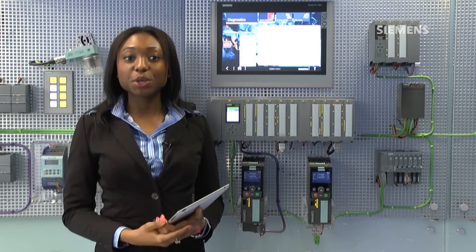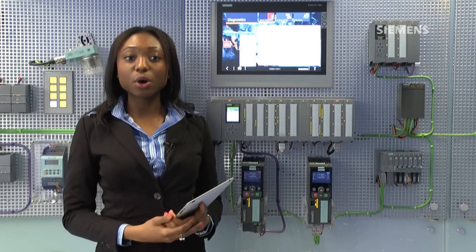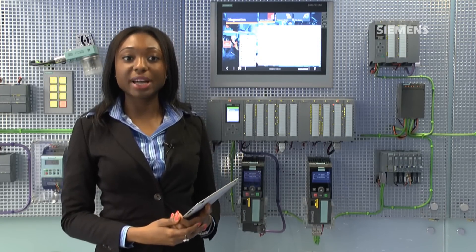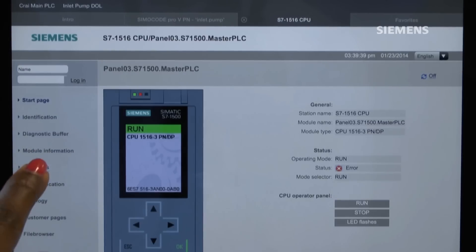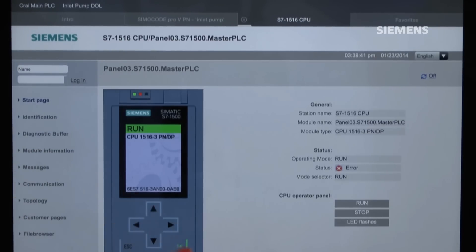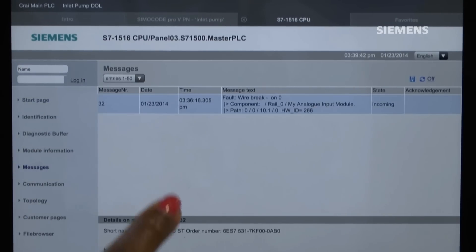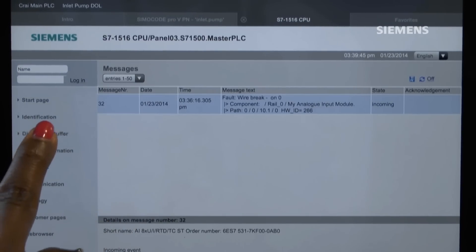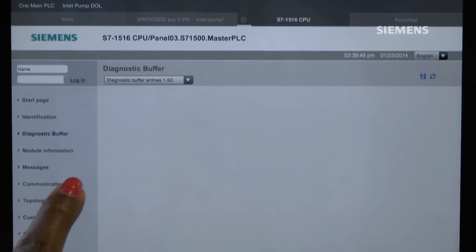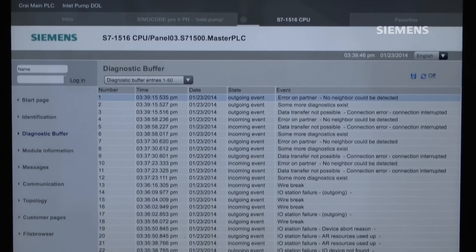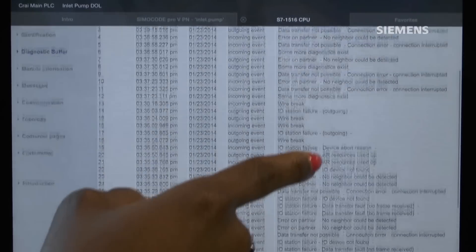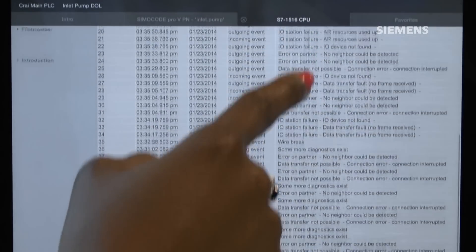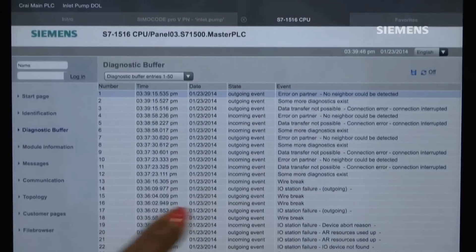The CPU web server also provides access to the controller's diagnostic buffer, which is a log of diagnostic events. This can be saved as a CSV file for interpreting later.